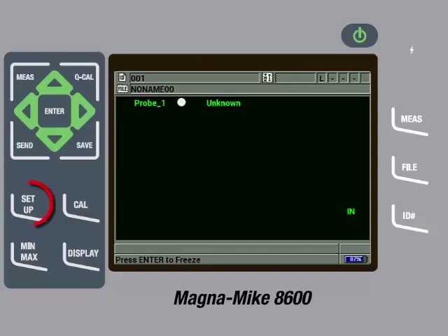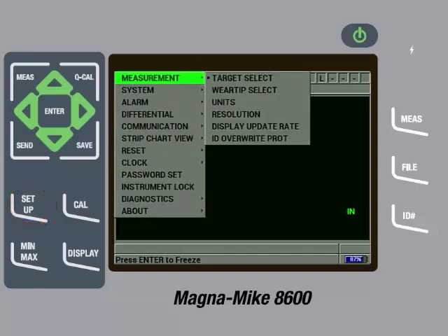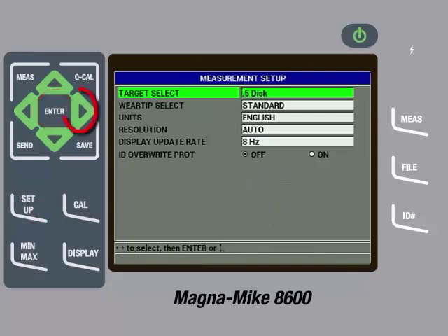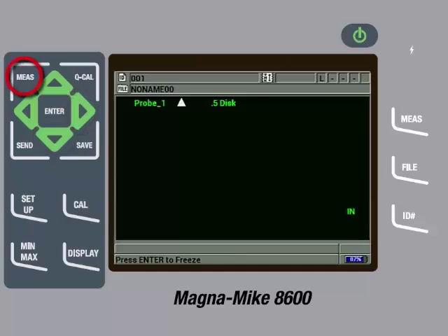To do this, press the Setup key. Then, with Measurement highlighted, press the right arrow so Target Select is highlighted, then press the Enter key. Press the right arrow so 0.5 disc is selected. Since we are using the chisel wear cap, we also need to change the wear tip select. To do this, press the down arrow, then press the right arrow to change the wear tip select to chisel. Then press the Measure key. On the main measurement screen, the instrument will now display a white triangle to represent the chisel wear cap, and it will show 0.5 disc for the target being used.